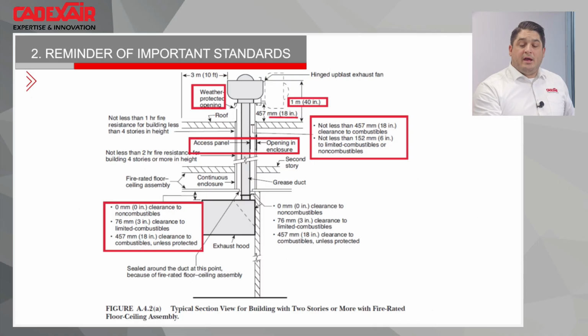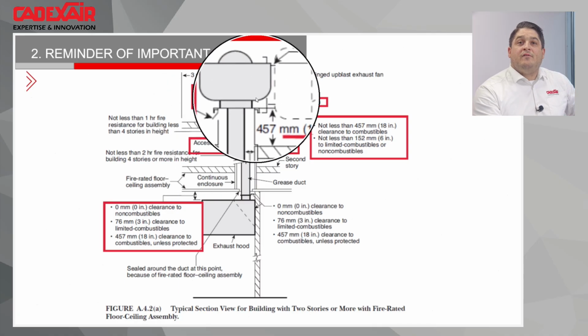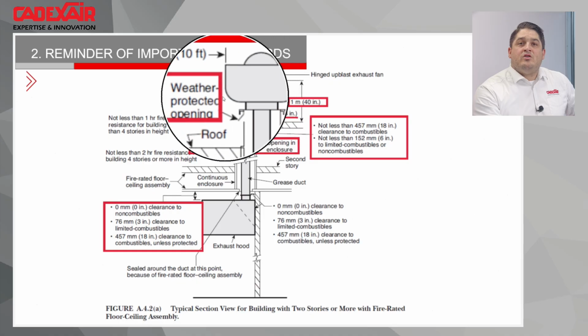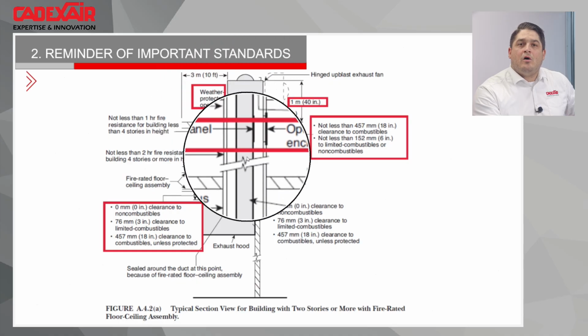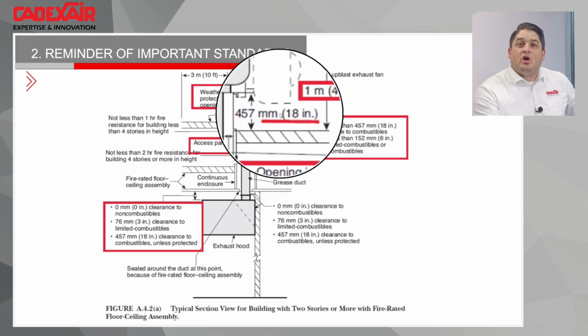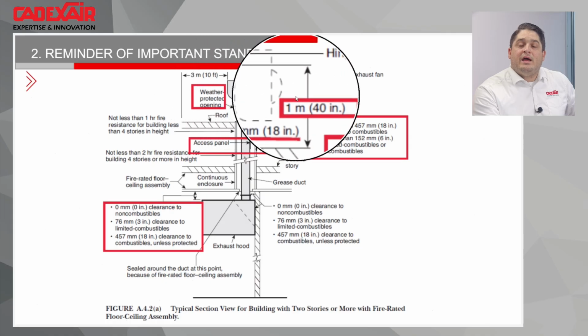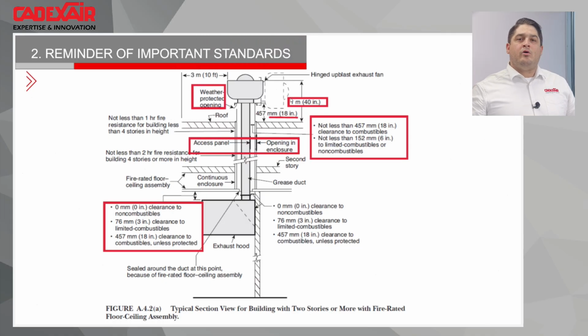And there are a few things we saw in this picture. As soon as you have an upblast fan like this, you're supposed to have hinges to be able to clean inside of the fan and also to clean the ductwork. They will say the curb needs to be 18 inches high, and the point of discharge of any fan needs to be over 40 inches. But I will say it's all standard in the industry, but sometimes it's good to know.